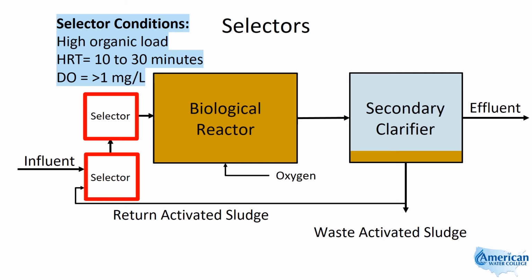In these selectors, typically the hydraulic retention time is 10 to 30 minutes, and the dissolved oxygen is maintained above 1 milligram per liter.